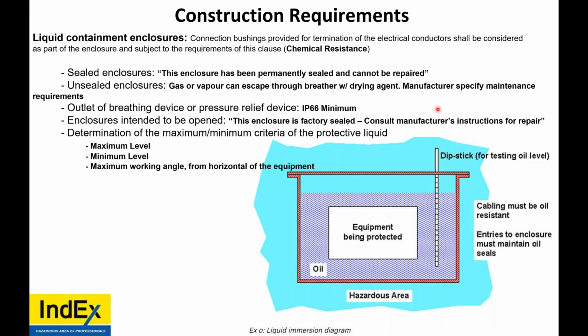Now, determination of the maximum and minimum criteria for the protective liquid, you need to know its maximum level, its minimum level, and the maximum working angle of the equipment. So if a transformer or whatever device is full of oil, at which angle can it be mounted on the ground? It may be on an angle. There may be vibrations that make the oil level move. So it needs to be able to withstand that.